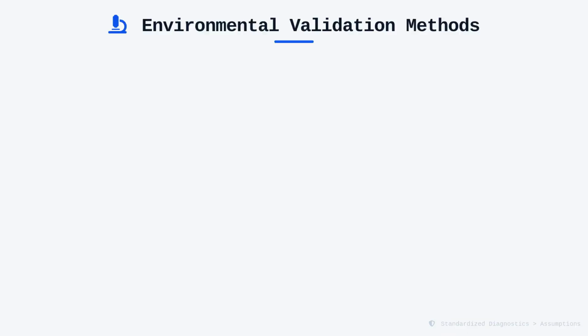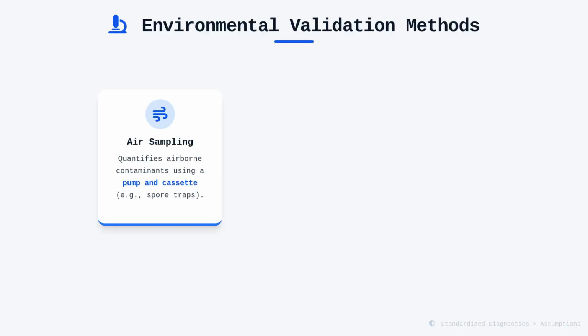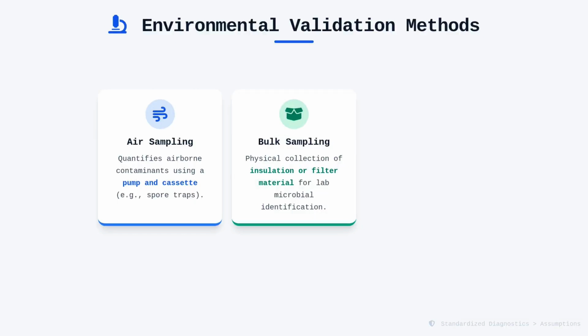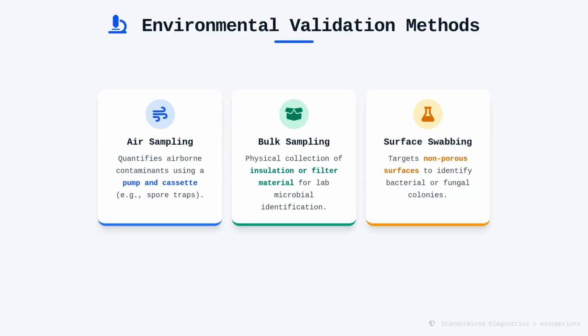When we transition from mechanical cleaning to environmental validation, we must rely on standardized diagnostic methods rather than assumptions. Air sampling is the most common technique used to quantify airborne contaminants, typically involving a pump that pulls air through a cassette containing a collection medium, such as a spore trap. Bulk sampling, on the other hand, requires the physical collection of material, like a piece of insulation or a section of a filter, to be analyzed in a laboratory setting for microbial identification. Surface swabbing is often used when visual contamination is suspected on non-porous surfaces, allowing for the identification of specific fungal or bacterial colonies that might not be readily aerosolized.